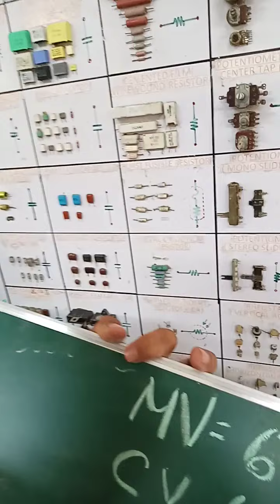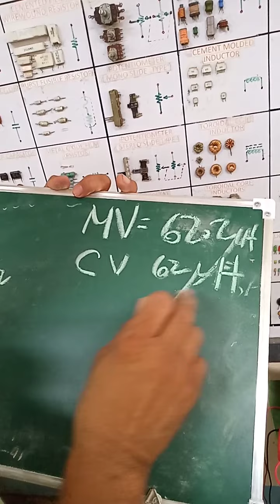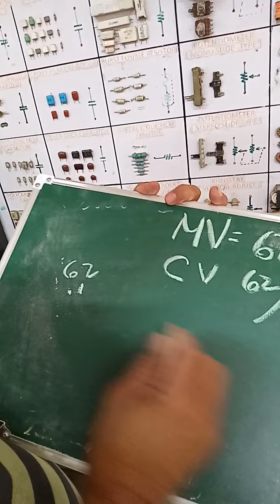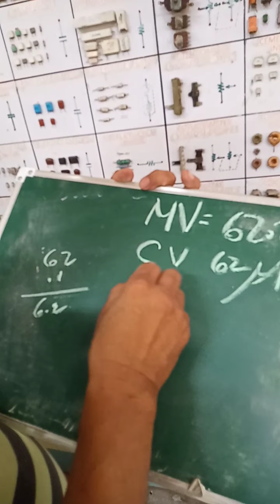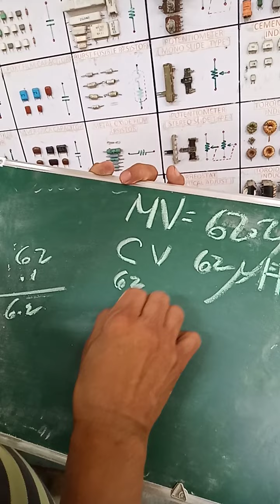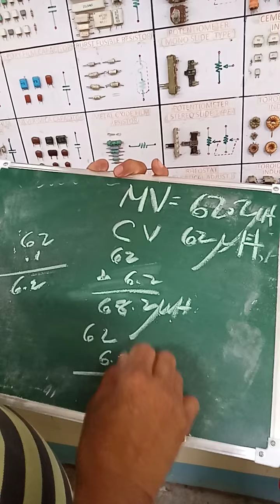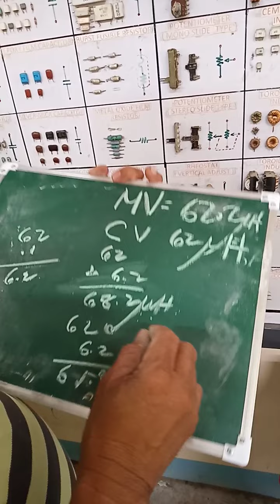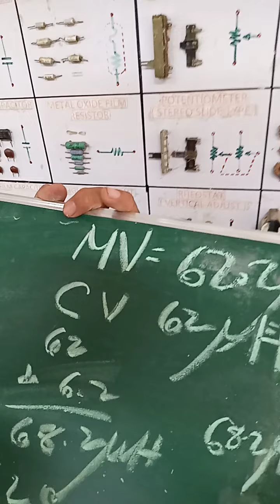Let us determine if this measured value is still tolerable. 62 times 0.1, because the tolerance is 10%. So convert it into a decimal number, and it is 0.1 as the corresponding decimal number of that percentage. So this is 6.2, the product. To get the maximum, the 62 coded value plus 6.2 is 68.2 microhenry. And for the minimum, 62 minus 6.2.